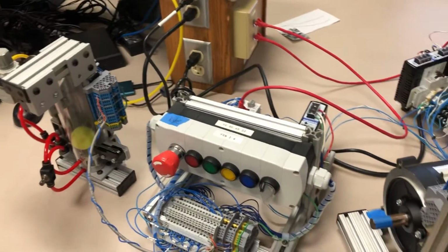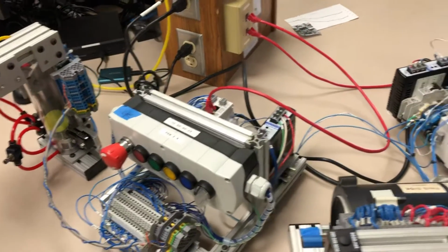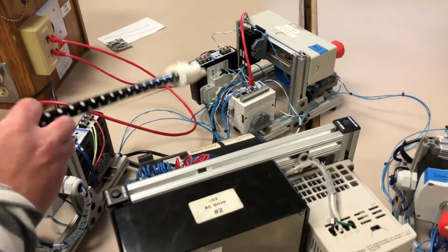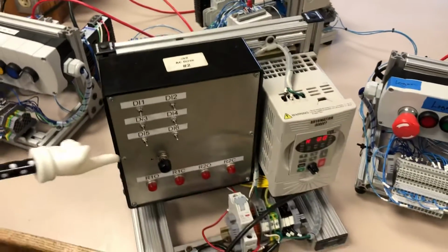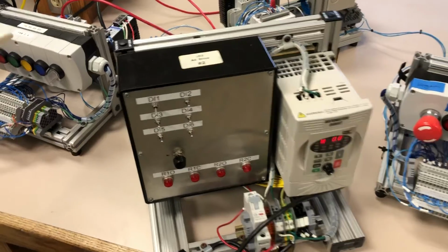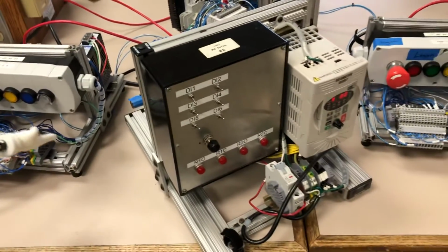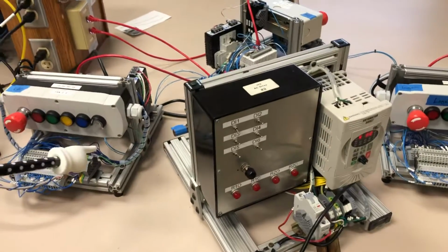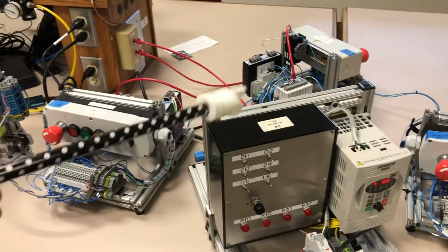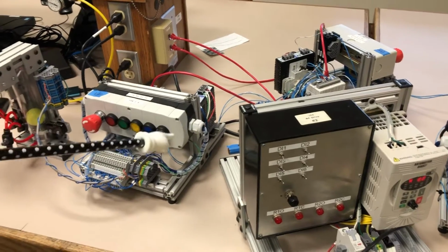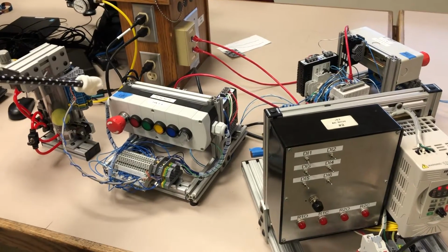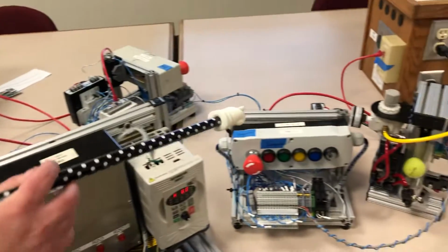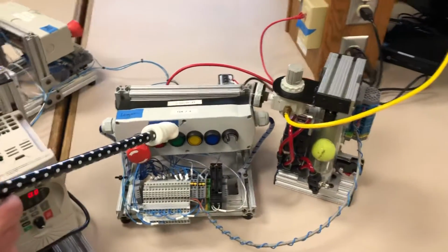When it is done shooting, it will send a signal to the secondary PLC, which will send a signal to the GS2 to tell the motor to turn on and ramp up to 40 hertz. Once the motor is at 40 hertz, the secondary PLC will send a signal back to the primary PLC, which will then send a signal to the other secondary PLC controlling the second ball shooter.